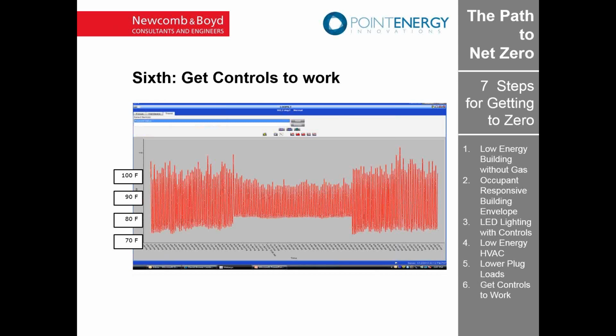Control systems, by and large, aren't working very well in buildings. This is a graph of a valve for hot water that should just be modulating smoothly, but instead it's going up and down, on and off, open and close. You see that everywhere in control systems. There's a whole industry born to handle this—it's called commissioning—but fundamentally the control systems aren't working correctly. So there's a big opportunity for new technology, improved technology, to come and basically displace what we currently have.